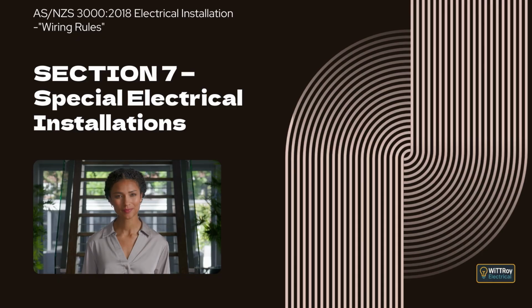Clause 7.5.12.1 General. This clause explains that the separation of extra-low voltage circuits must be verified by insulation resistance testing. It clarifies that different verification methods apply depending on whether protection is achieved by SELV or PELV.